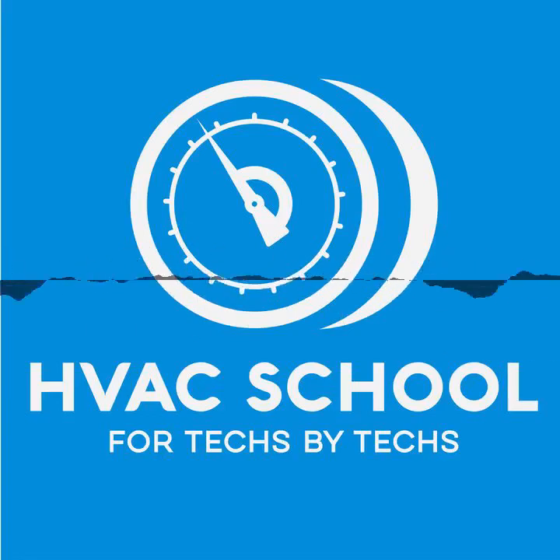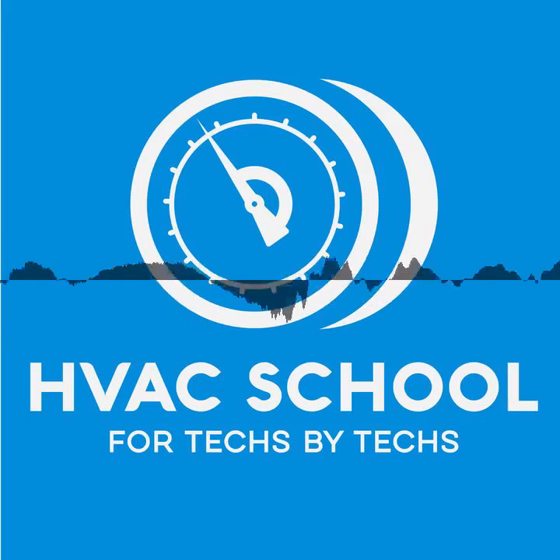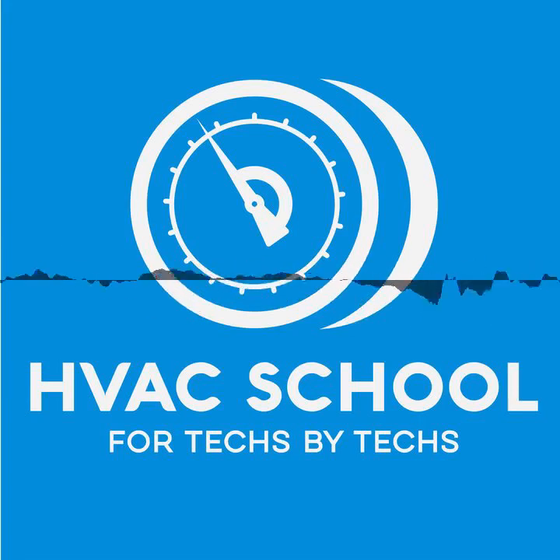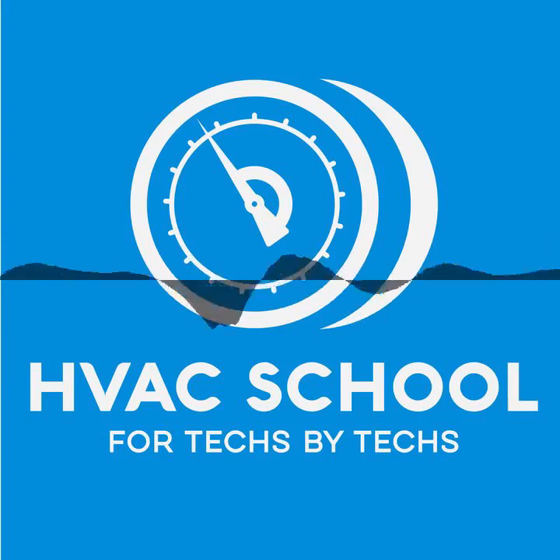All right, if you guys have listened to this podcast for any amount of time, you know that I kind of have a little bit of a crush on the Testo 605i. It's just a stupendous, can I say stupendous and not have it seem like hyperbole? I'm going to choose to say stupendous. It is a stupendous tool for the investment that you spend on it. It is a great thermal hygrometer. And for those of you who are like, what the heck is a thermal hygrometer? Well, let me tell you. A thermal hygrometer is basically a digital psychrometer. That's another term for it. And it measures wet bulb, dry bulb, relative humidity. The dew point, it can extract all of those.